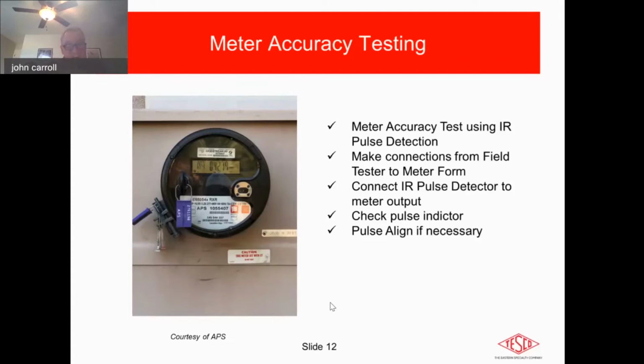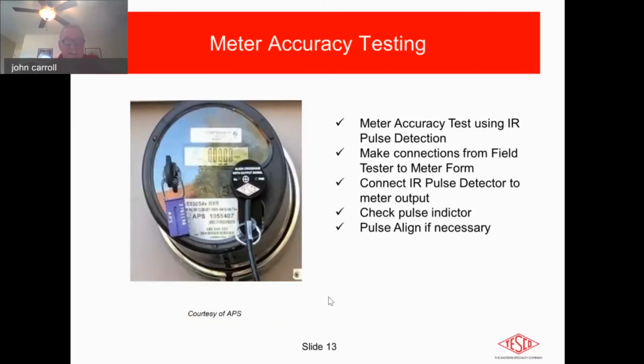Pulse align if necessary. You don't always have to do that, but it's a really interesting way to actually do a pulse alignment on it, which is a very useful feature before you're running a test. So I've magnified this one a little bit. It's not brilliantly in focus, but you can get the idea. And you can see on the front of this meter pickup, we have a power indication. So immediately that is connected on there. That will be a green light to let you know you've got power. And if a pulse is picked up, that little red LED will light up.